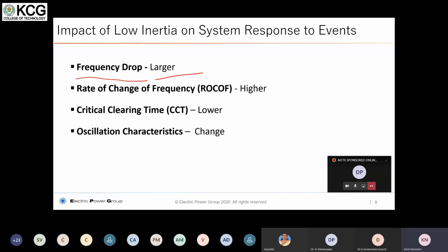The third metric is the critical clearing time that is available for a line. What we mean by this is that, for a given line, say, for example, a 500 kV line carrying 1000 megawatts of power, within its thermal limits, you should make sure that when a fault happens, you clear the fault in a particular time frame. That is called the critical clearing time. If you do not do that, then either the transmission line will melt down, or the stability of the system is affected, or both can happen in the system.